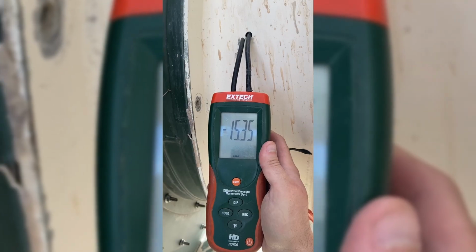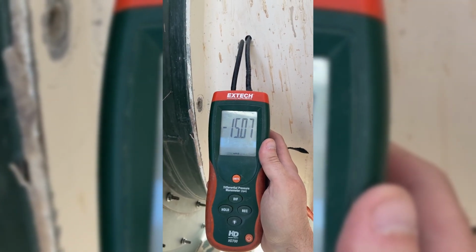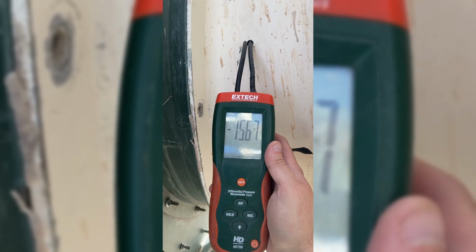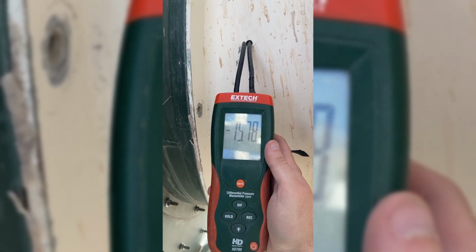But essentially, one big thing to do is to take static pressures. Just put a hole in the duct, put a tube in, measure the pressure at that single point. Not a pitot tube, not a flow, but just measure the pressure at points, and you can measure before and after equipment. And if anybody's familiar with baghouse differentials, that's essentially how it works. You'll have a reading on the dirty side and a reading on the clean side. And the difference is the pressure drop across the baghouse. If you've got all these filters clogged, you're going to have a real high pressure drop.